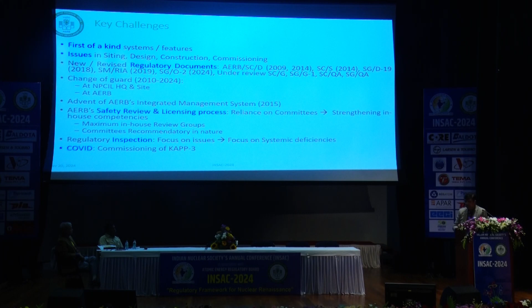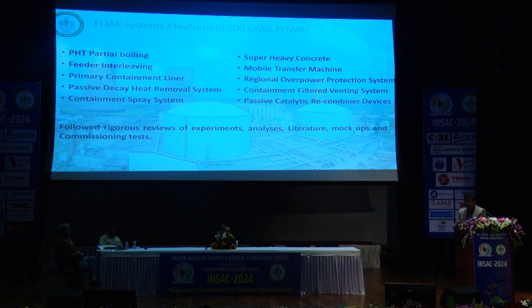Then going into the technical details now, these are the first of a kind systems and features in 700 megawatt PHWRs, and as I was mentioning, we followed a rigorous review of experiments, safety analysis, literature, mock-ups and commissioning tests for review and acceptance of these first of a kind systems and features. I'll try to give you a glimpse of these. So PHT partial boiling, around 2 to 3% partial boiling is allowed from the 11th bundle onwards. We have 12 bundles in the coolant channel. From the 11th bundle onwards, there is some partial boiling allowed.